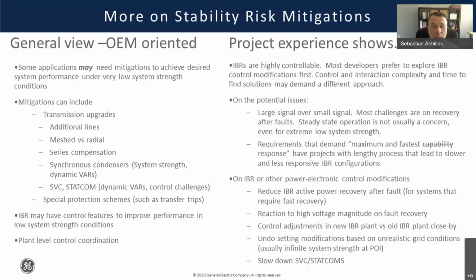Now, we do see that very often the solution to these problems, although they're technologically possible, take quite a bit of time. These control interactions have a complexity that goes down to the lines of code in the controller of vendor 1 and the controller of vendor 2, and finding out what specifically is causing this and solving it could take quite a bit of time. So sometimes it takes so long to solve, or there are some data exchange aspects that will be difficult to resolve, that this ends up not being the best option. So you have this very flexible IBRs, but the complexity of the controls and how the different functions interact result in a complexity that sometimes may create problems that are difficult to resolve.